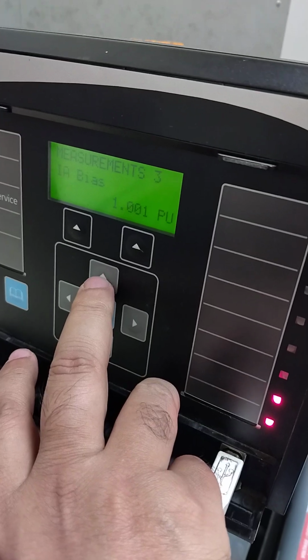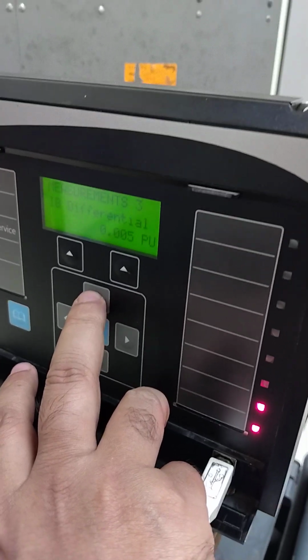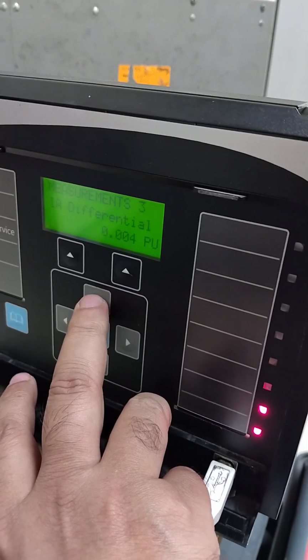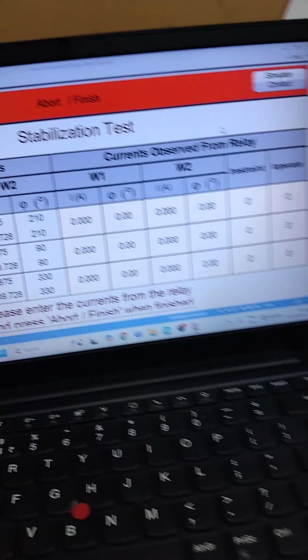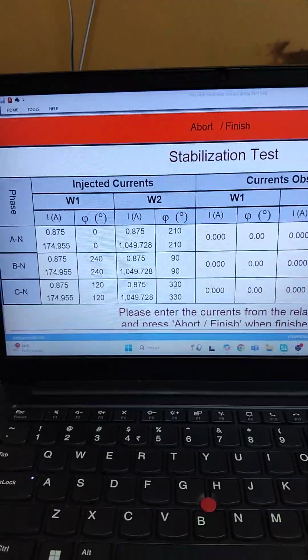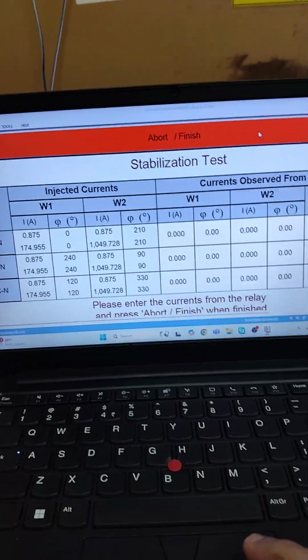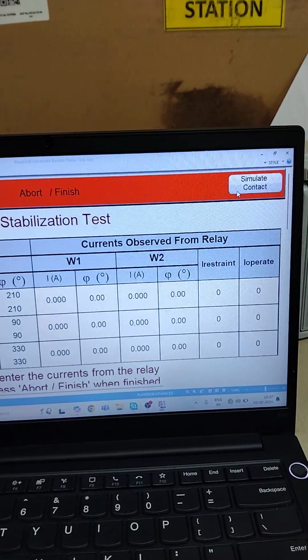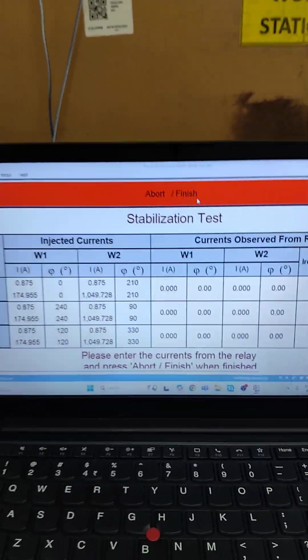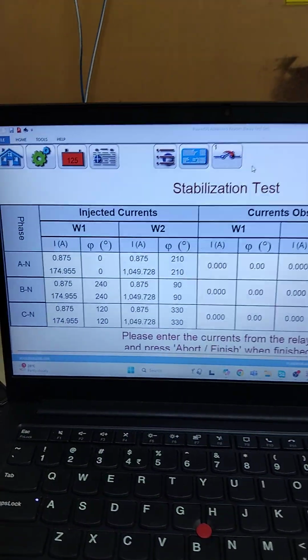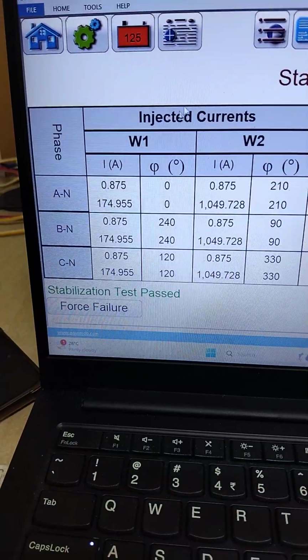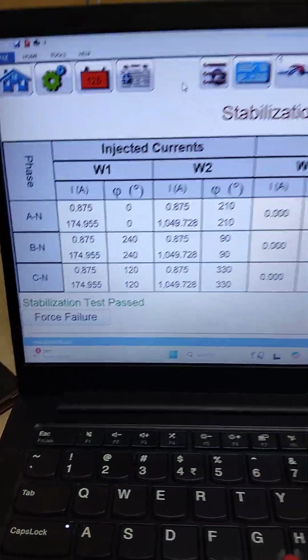So if you get any differential current, that means your stability is not true and you need to check your configuration or setting or whatever, or maybe the test kit injection, what you are doing. So once you finish it, since it has not received any trip command from the device RL1 output, as soon as I close it, it will give you stabilization test passed, because there was no tripping. Now we can check the timing.